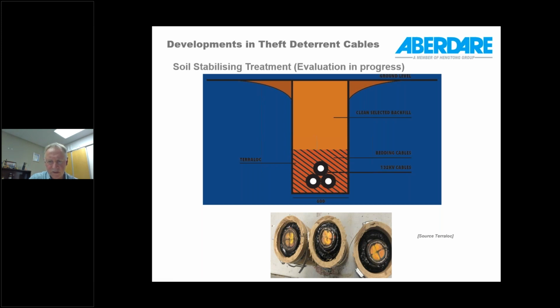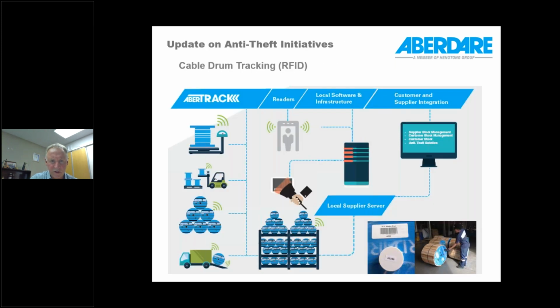So we haven't concluded our testing, and as soon as we have more information available, we'll make that known. The last slide, I think, is cable drum tracking. It's a radio frequency identification device which gets installed in the drums. It looks like this. Obviously, once the cable is off the drum, there's no way of tracing the cable. There's no RFID in the cable, so for a standalone cable, the solution is not suitable.